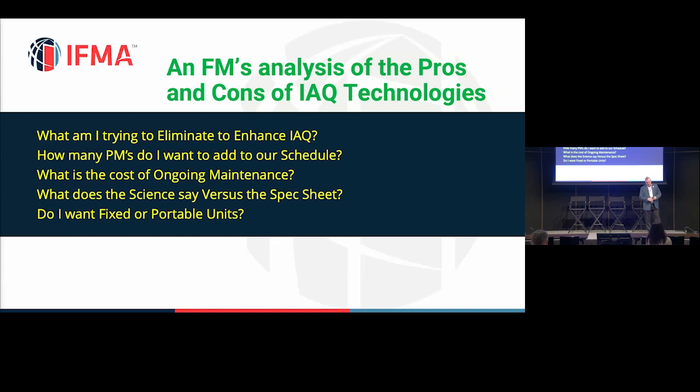Yeah, and that's a valid point. Everybody wanted to rush out and put MERV 11s, MERV 13s, because MERV 13s are similar to HEPA. But like you said, the back pressure on your system, you'll blow it up. You can't just go throwing heavy filters in there and make it work. One of the other issues with air quality devices, filtration systems, or UV or APCO is placement.